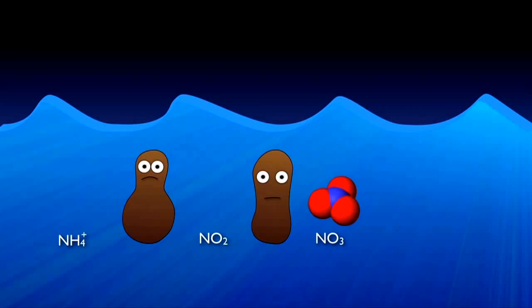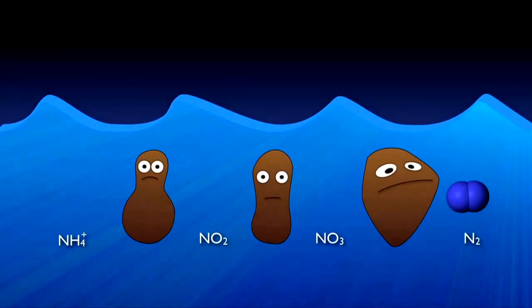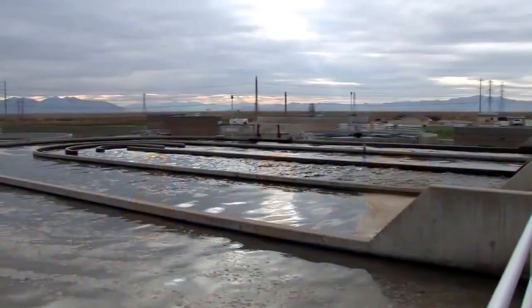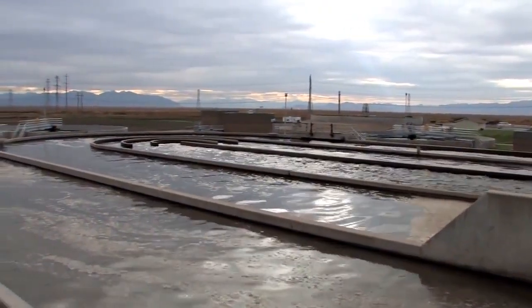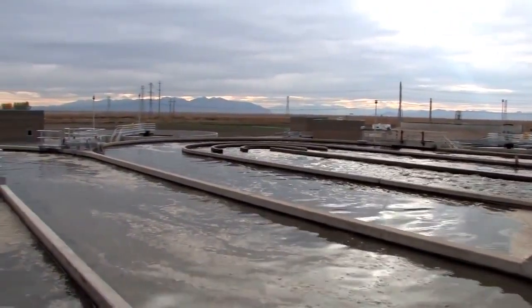As dissolved oxygen is depleted by the nitrifiers and other organisms in the basin, other specialized heterotrophic bacteria — denitrifiers — are able to thrive by using the oxygen attached to nitrate molecules for respiration, creating nitrogen gas as a byproduct. The nitrogen gas then simply bubbles out of the water into the atmosphere. Now let's go back to the beginning and take a closer look at each of these important steps in the nitrogen removal process.